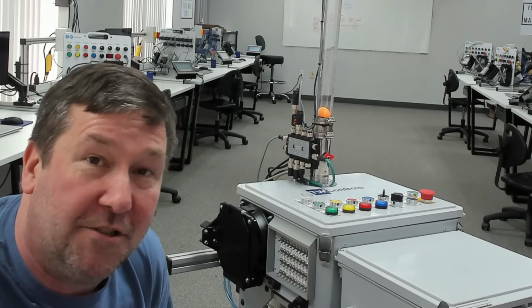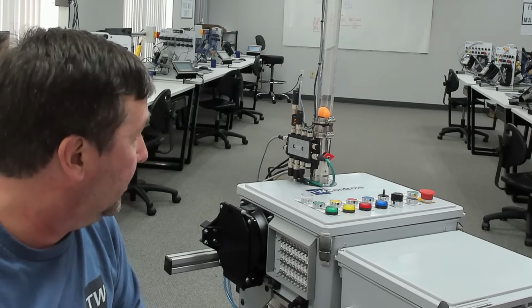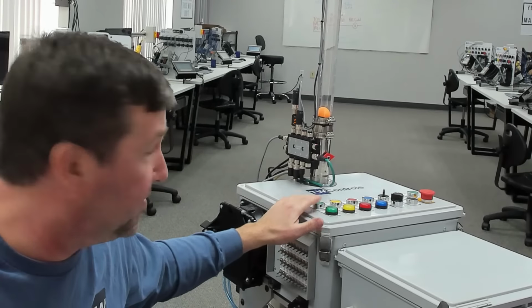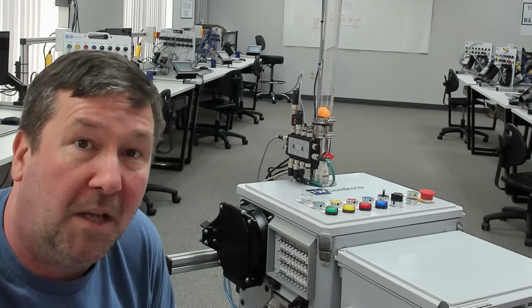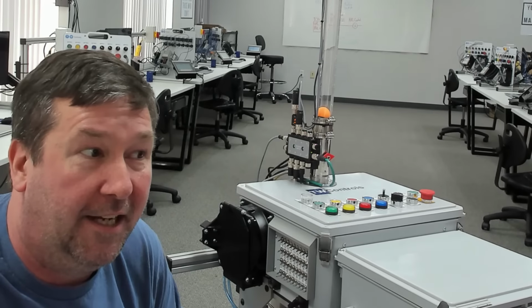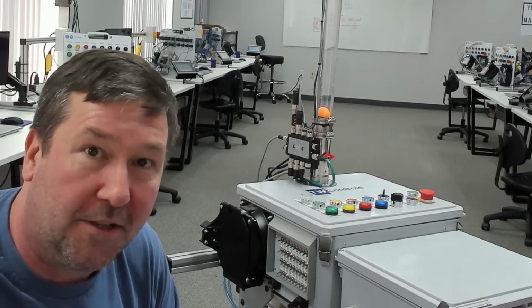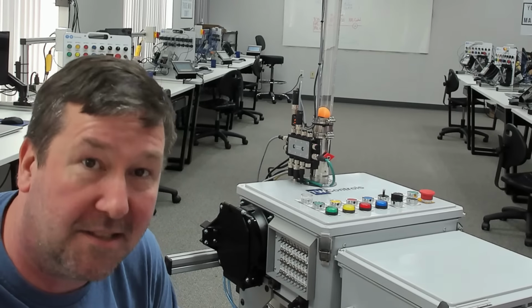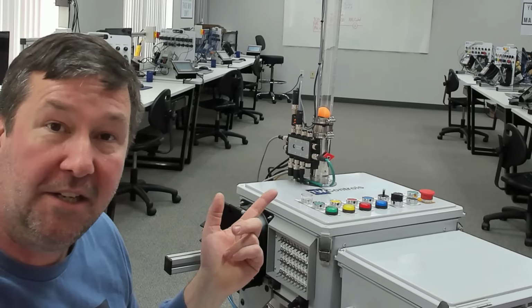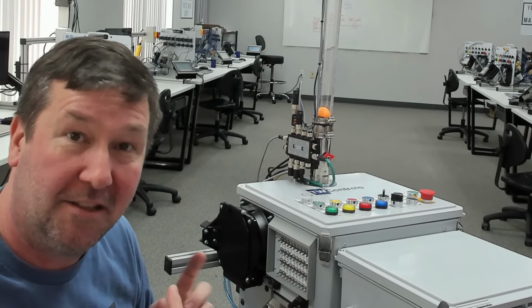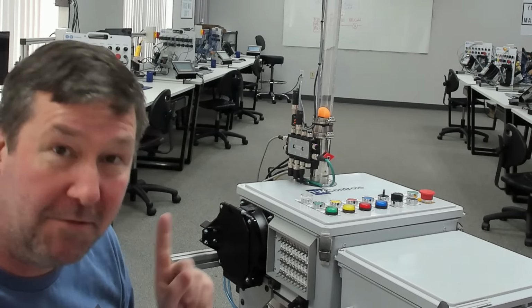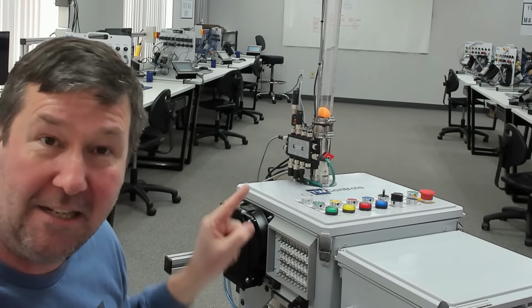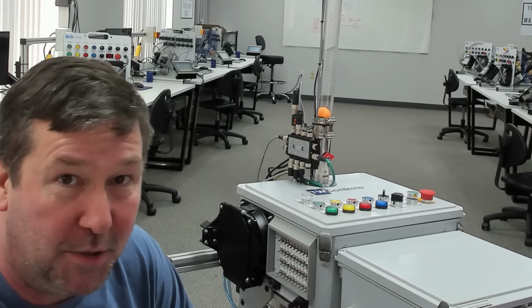I ask them, well, what should we go check? And they'll say, well, I think we probably need to check the green buttons. I ask, do they do action? They always say, well, yeah, they start the machine. I say, no, they do not start the machine. The PLC reads the buttons. Those are inputs. If it was an action item, the PLC would be magically making those buttons move.